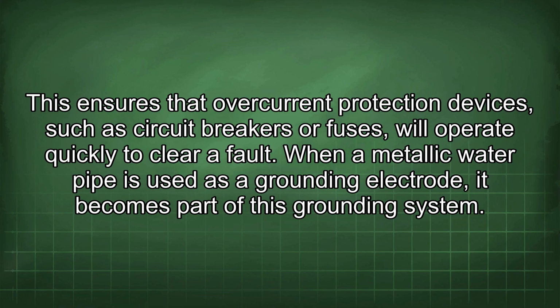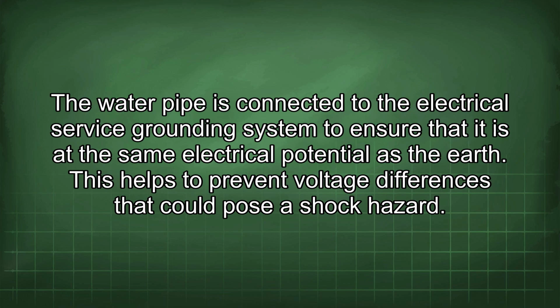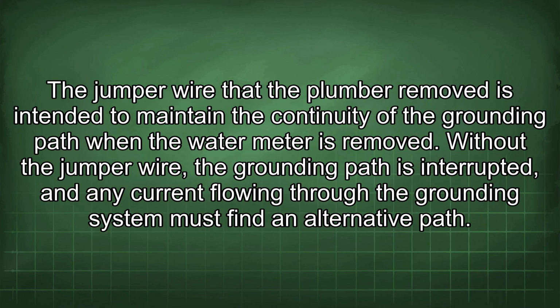When a metallic water pipe is used as a grounding electrode, it becomes part of this grounding system. The water pipe is connected to the electrical service grounding system to ensure that it is at the same electrical potential as the earth. This helps to prevent voltage differences that could pose a shock hazard. The jumper wire that the plumber removed is intended to maintain the continuity of the grounding path when the water meter is removed. Without the jumper wire, the grounding path is interrupted, and any current flowing through the grounding system must find an alternative path.